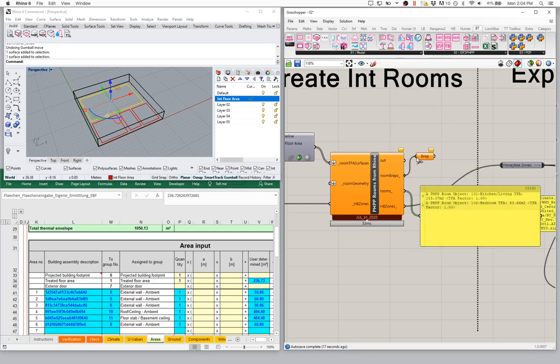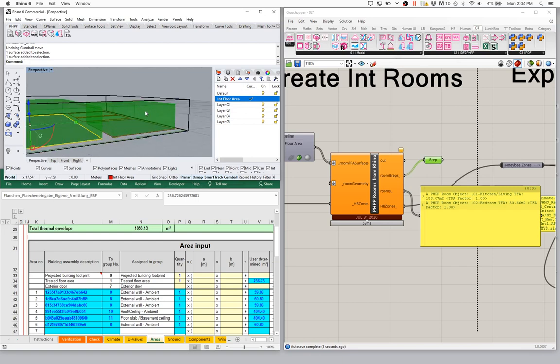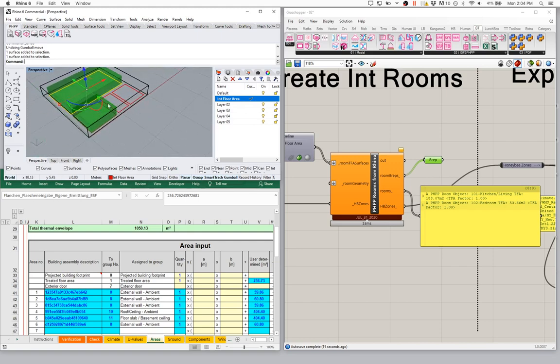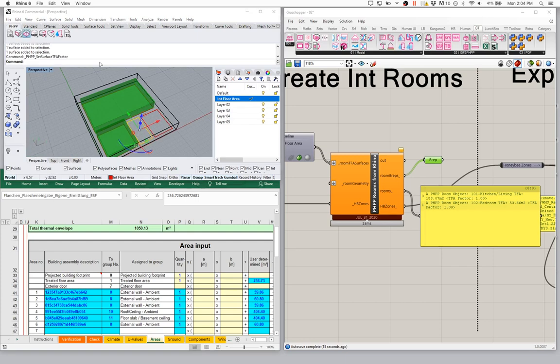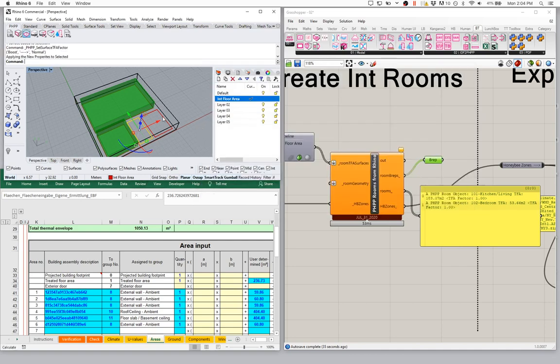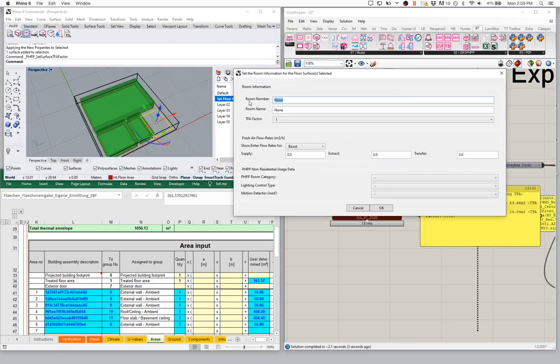If we want to see the room volumes being created, I can output a preview of those room volumes, and notice it's performing that two and a half meter extrusion on those room shapes based on the surface itself. Let's finish entering our information. Room 103 — let's call this the hallway — with an extract of about 12 CFM at normal fan speed. And lastly, room 104 — let's make this a mechanical room — also with 12 CFM of extract at normal fan speed. OK.